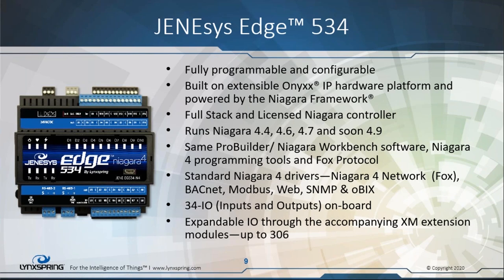Onyxx is the actual product you see here, but without Niagara on it. We were entertaining the idea of creating an onboard I/O programmable controller to replace products soon to become end-of-life, the Jace 3.6 products. We'd had a lot of success with OEMs putting Jaces with I/O on equipment, and we were told those were end-of-life, so we wanted something to replace them and give our customers an option. What better than building a product that's programmable with I/O on board, 34 points, exactly the same amount of I/O as on the I/O module.